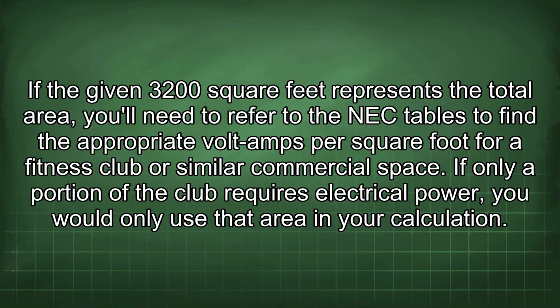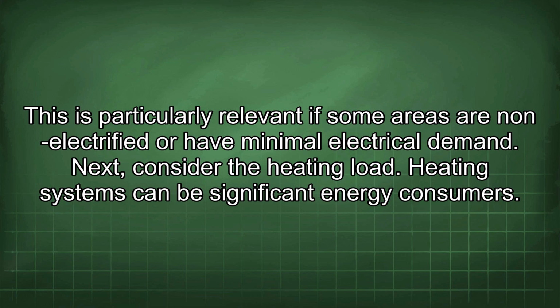If the given 3,200 square feet represents the total area, you'll need to refer to the NEC tables to find the appropriate volt amps per square foot for a fitness club or similar commercial space. If only a portion of the club requires electrical power, you would only use that area in your calculation. This is particularly relevant if some areas are non-electrified or have minimal electrical demand. Next, consider the heating load. Heating systems can be significant energy consumers.